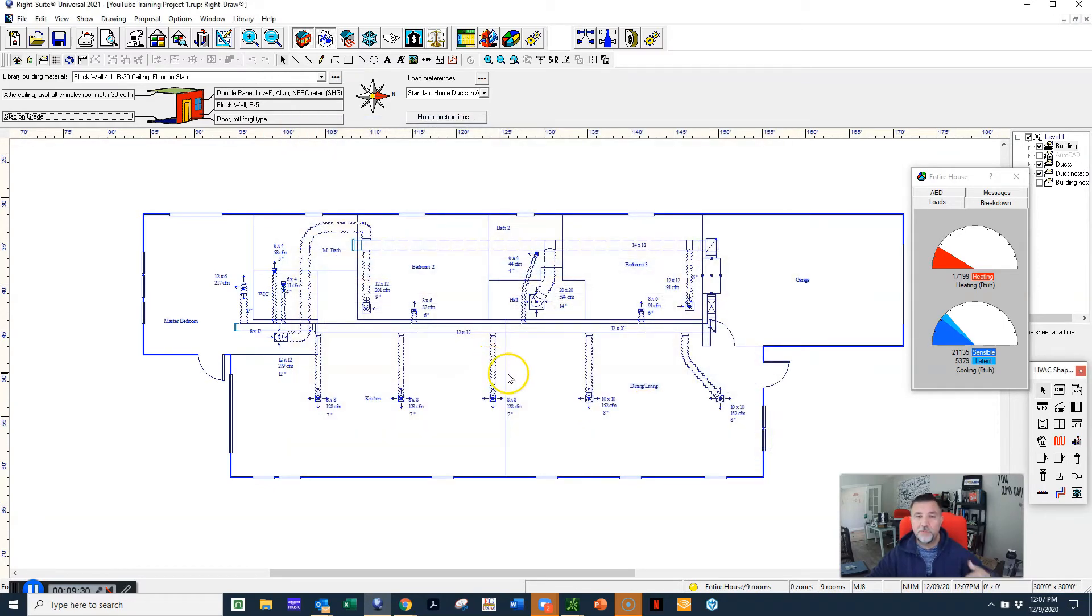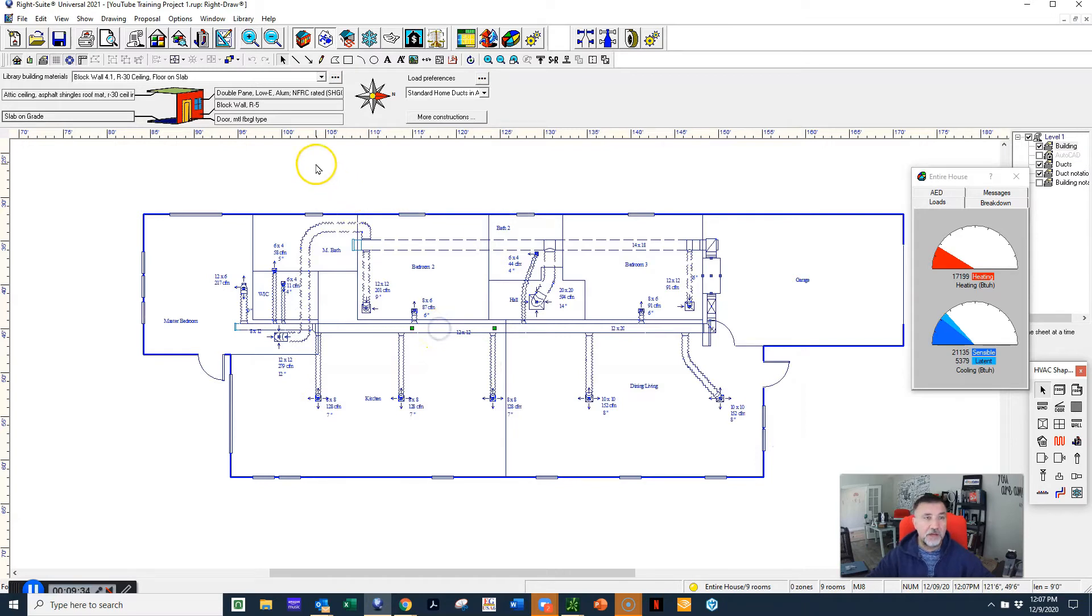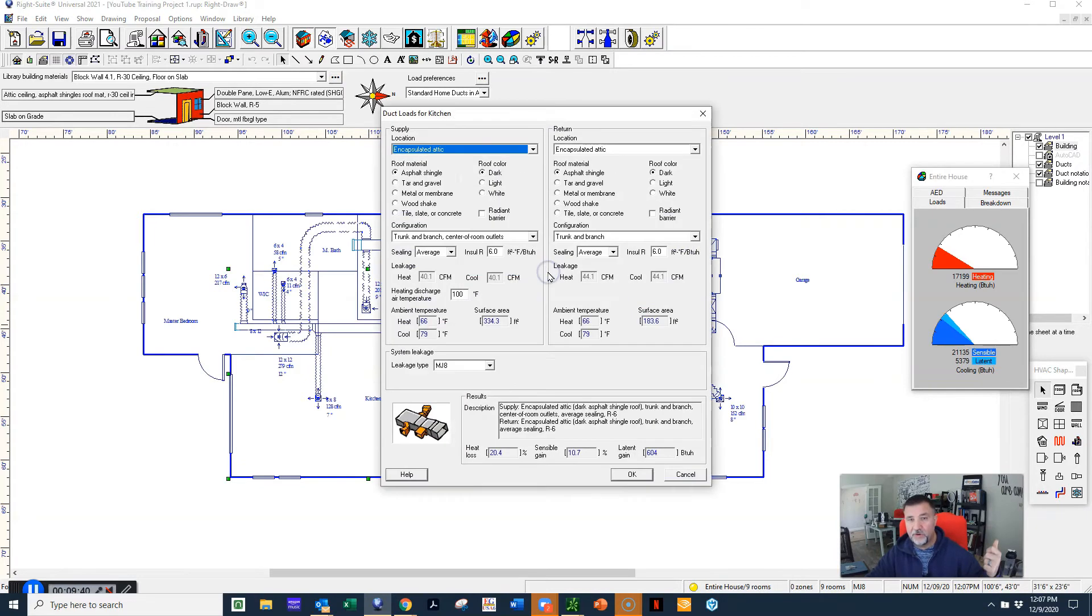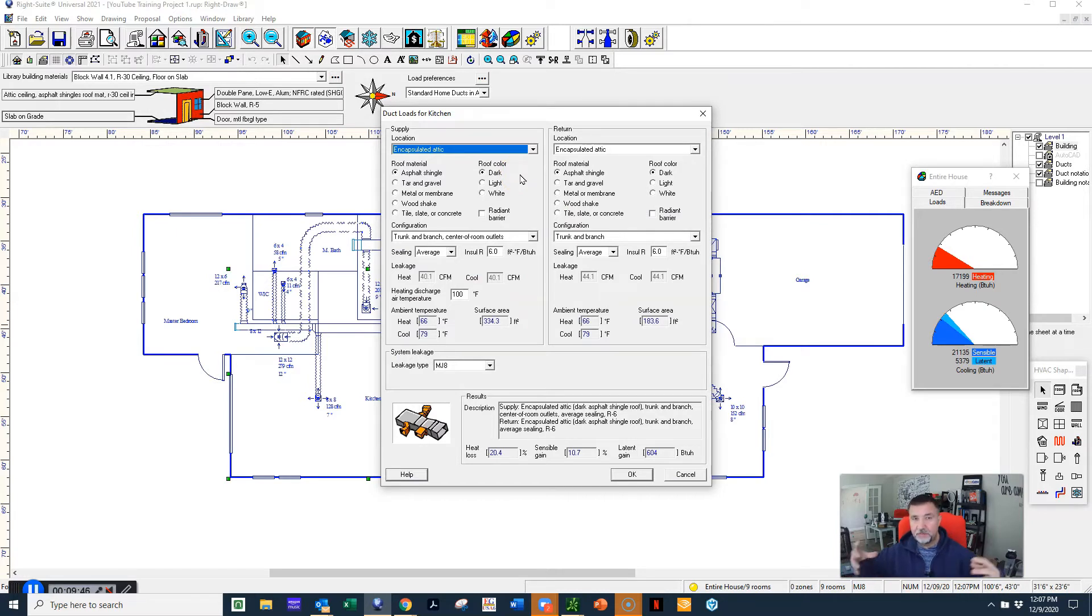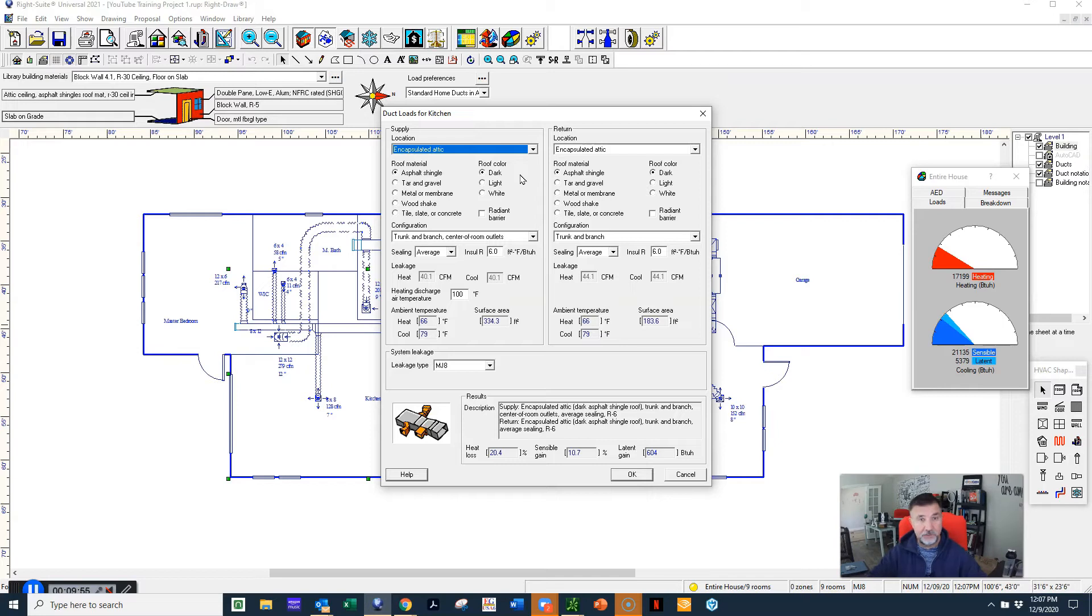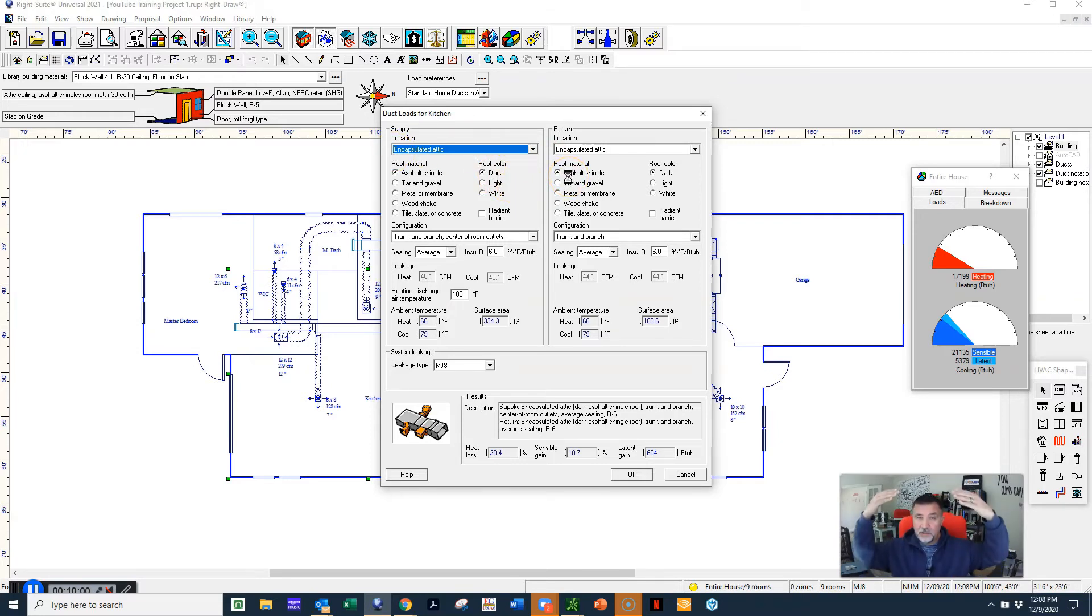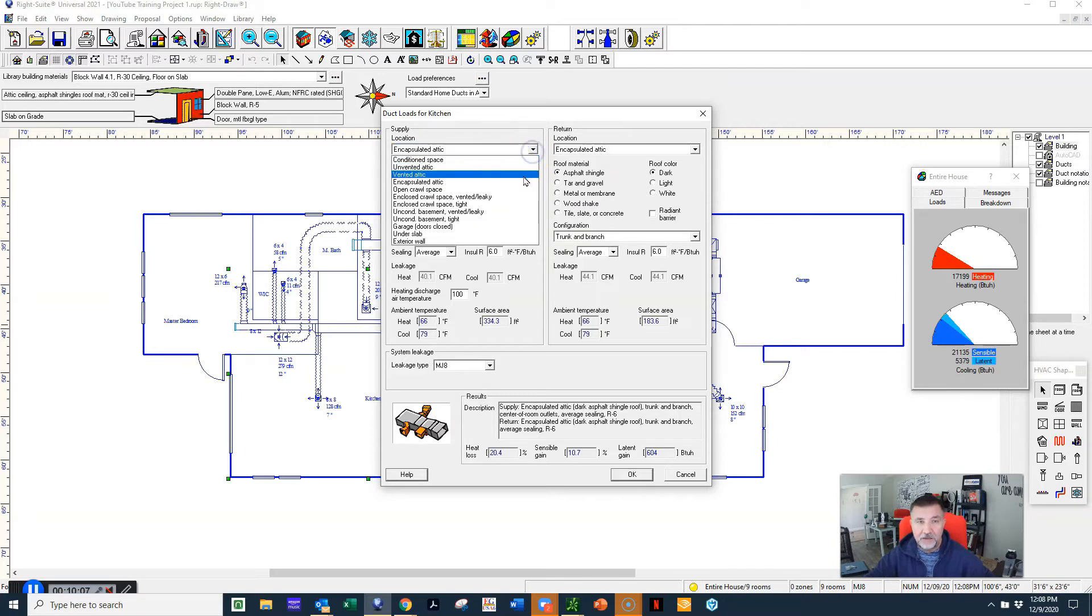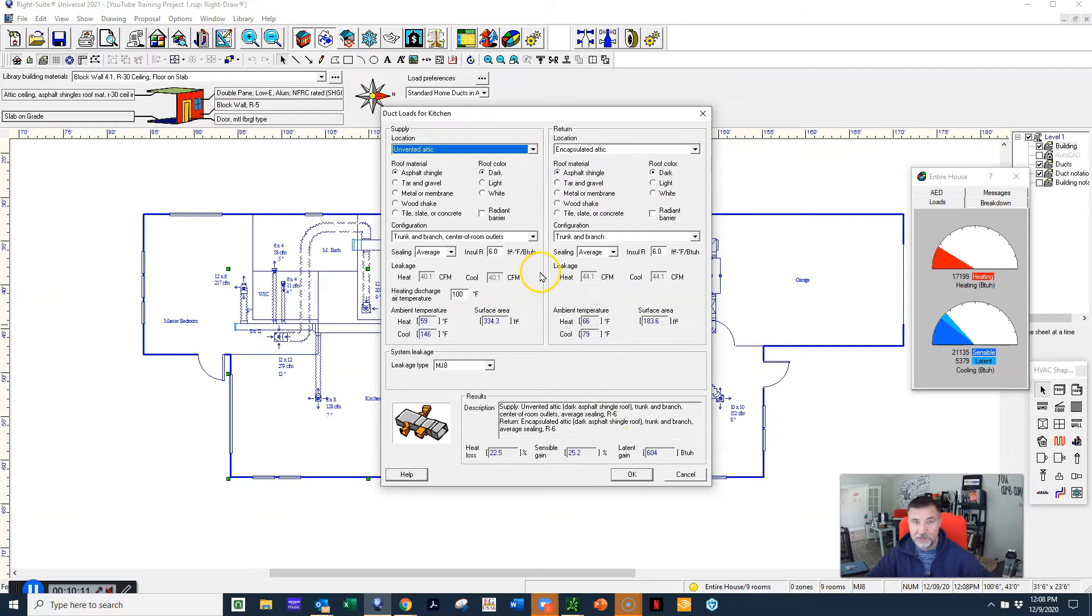Everything that we built—this is why it's important. Even when you're looking at your ductwork, this is why it's so important when you're talking about those 400 to 500 square foot per ton. It's so important to understand all the different complexities that come into the Manual J to ensure that the proper amount of heat that could potentially be absorbed by that item, such as the ductwork. If I have an encapsulated attic, which means that the insulation is on the roof deck, which means my attic is going to be much cooler, and I factor this as an unvented attic.